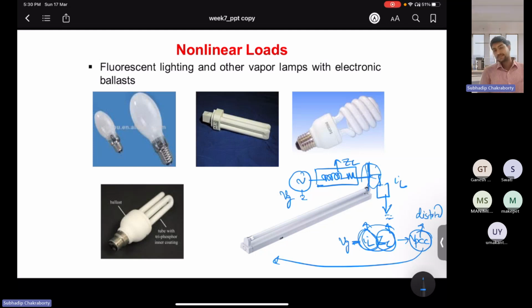Yes, can anyone tell me? In a weak grid scenario. This is prevalent in a weak grid scenario. Weak grid is observed in islands or deserts or remote villages where you have long lengths of transmission lines, which accumulate, resulting in relatively larger values of X and R, which leads to an increment in the line impedance. So can anyone tell the effect? What is the effect on the rotating magnetic field of rotating machines?